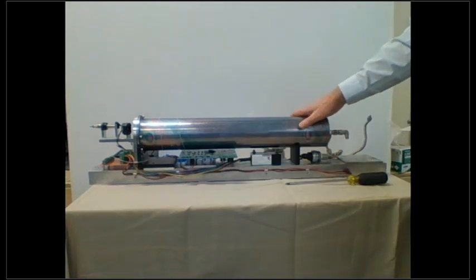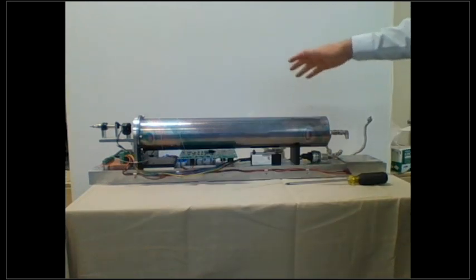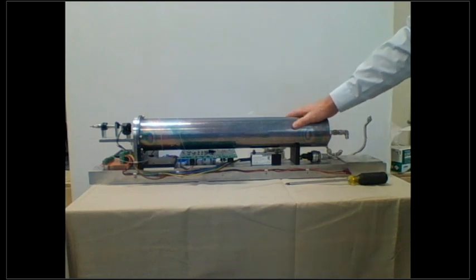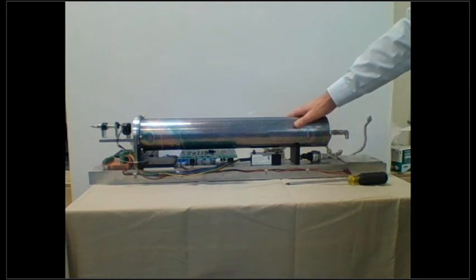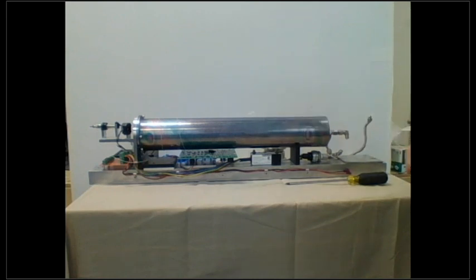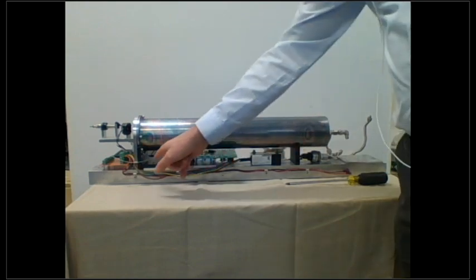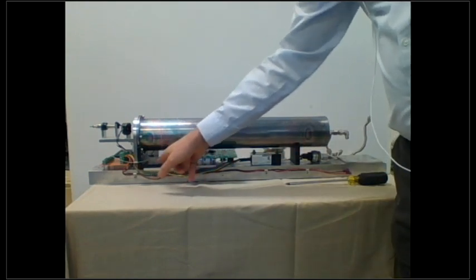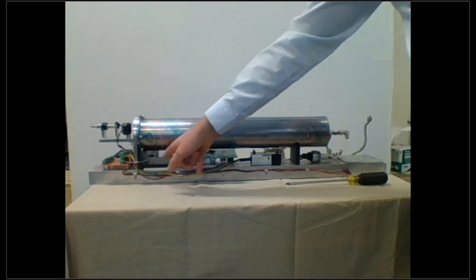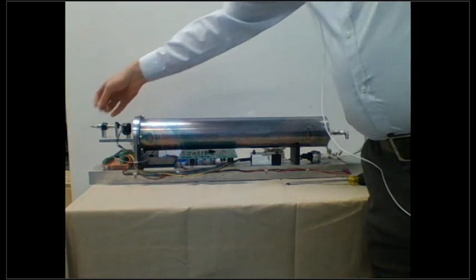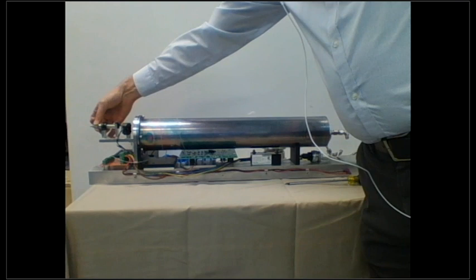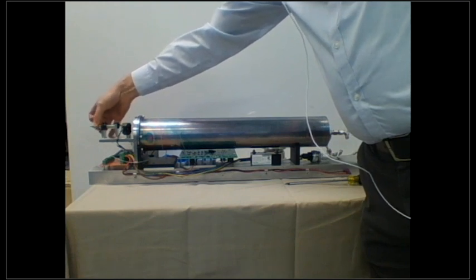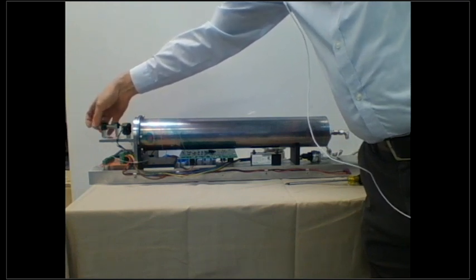The other thing I wanted to talk about is the cell itself. Now, it's unlikely if your sample conditioning is doing its job that you would need to go into the cell on a regular basis. But if something were to happen where it got flooded somehow, some liquid was able to get into it, the user does have access to the inside of the cell. So to take the cell off, there's basically 4 bolts here that hold the entire assembly down to the rail. You will have to undo the fiber optic cable from the laser launcher.